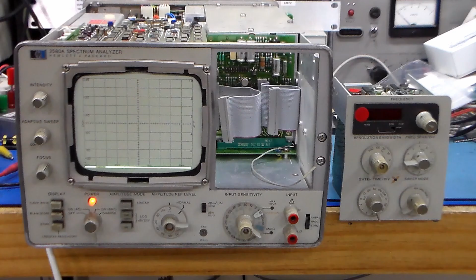This is where we measure the power supply volts on the HP3580A. We can check positive regulated 10 volts, which is good, negative regulated 10 volts, which is also good, and the 150 to 158 volts that drives the DC-DC converter for the accelerating voltage in the CRT. You can see it's 154.8, which is also in spec.